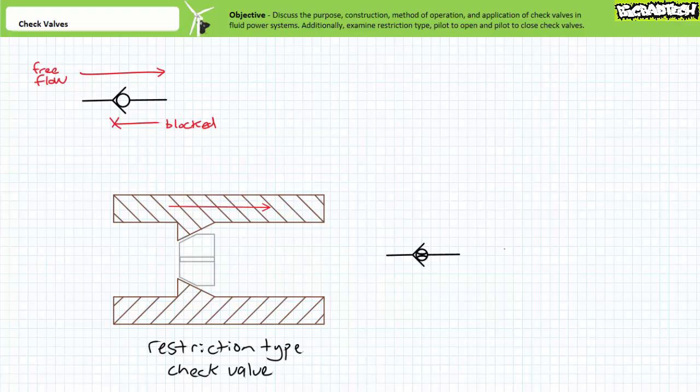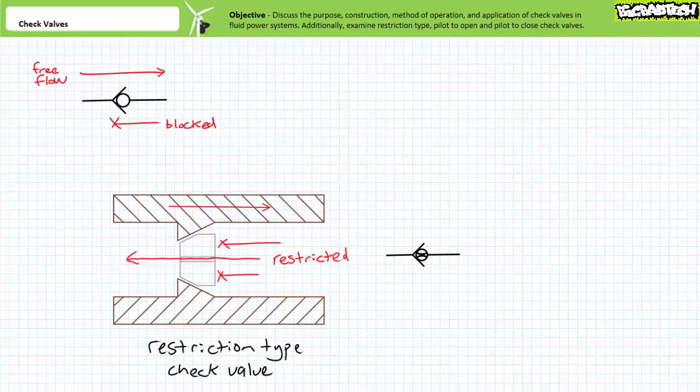A restriction type check valve is basically a regular poppet style check valve with a tiny orifice drilled through the poppet. When fluid enters in the free flow direction, the full poppet is pushed off the seat and fluid flows freely. When fluid enters in the restricted flow direction, the poppet is pushed onto the seat and fluid is forced to travel through the tiny orifice.